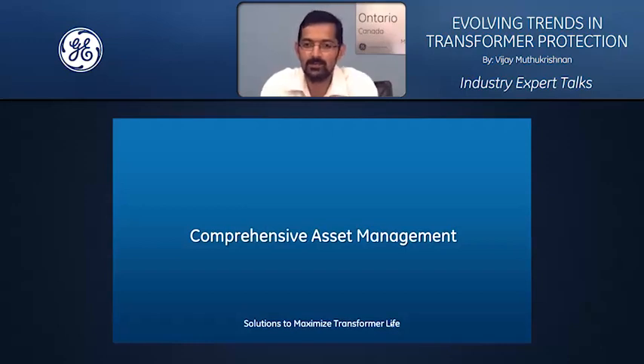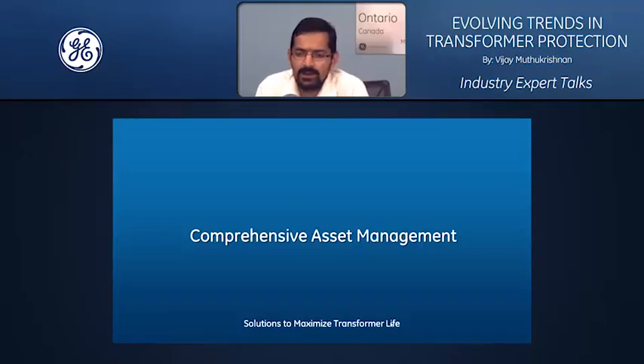All right, let's continue to the next area of exploration in this discussion. This is a very unique, evolving trend in the industry. When you think about a transformer protection relay, traditionally you only imagine its functionality to be that it detects a fault and trips the breaker when there is an internal fault, and stays stable when there is an external fault. This is the most simplified understanding of a transformer protection relay. With some metering and measurement functionalities, you have some capability of looking at what is happening in the transformer. But in the older technologies, we couldn't achieve much more.